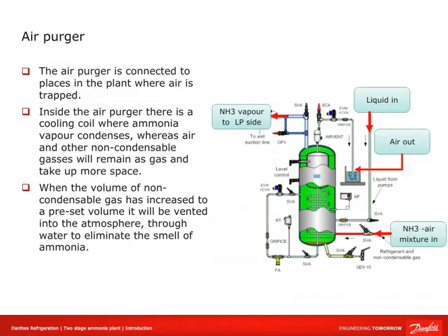The air purger is connected to places in the plant where air is trapped. Inside the air purger there is a cooling coil where ammonia vapor condenses, while air and other non-condensable gases remain in a gas state and take up more space. When the volume of non-condensable gas has increased to a preset volume, it is vented to the atmosphere through water to eliminate the smell of ammonia.